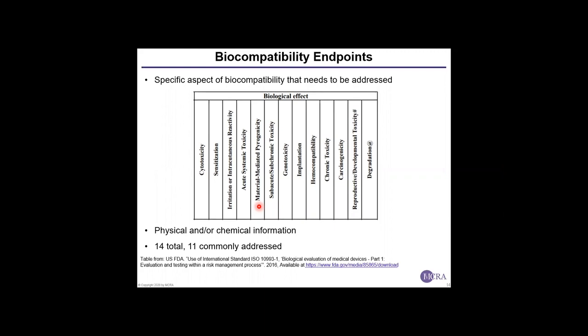So all in all, there are 14 of these biocompatibility endpoints, and 11 of these endpoints are commonly addressed for medical devices. One other thing to note is most devices won't address all 11 of those common endpoints, but instead a subset of those endpoints. And a key concept in biocompatibility is deciding which biocompatibility endpoints need to be assessed. And that's typically determined by two factors primarily.